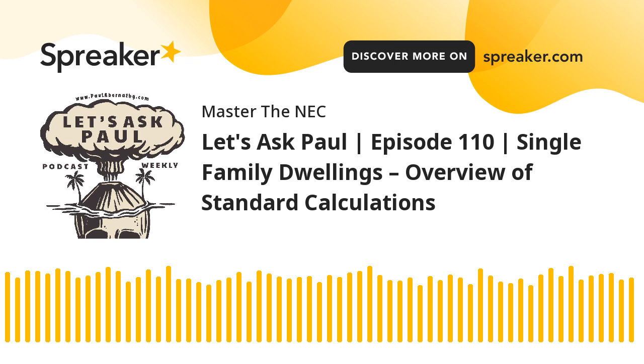When it comes to the clothes dryer and the cooking, you take the value that you got from your first calculation that you did for the standard, and you just multiply that by 70%. And that's the value you're going to use for your neutral. Now, if you're wondering, where do I get that, Paul? Where does it say take that value that I just calculated for the size of my clothes dryer, which is that 5,000 VA, you remember? You just simply take that and multiply that by 70%.